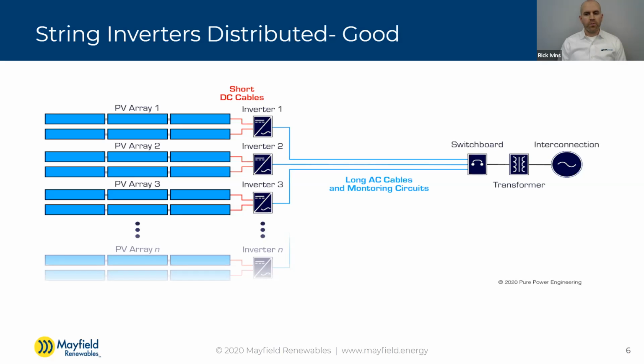I think that's because when string inverters first came out, they were first used on rooftops. With the rapid shutdown requirements coming up in the NEC, that 10-foot requirement in 2014, people wanted to spread these inverters out through the array, because having the inverter right next to the array it's fed by also addresses the rapid shutdown needs of that NEC. Then, as string inverters kept getting cheaper, people started using them on ground mounts in place of central inverters, applying the same approach as on the rooftop. They spread them all throughout without really thinking that ground mounts should be designed a little differently, since we don't have that rapid shutdown requirement to take into account.